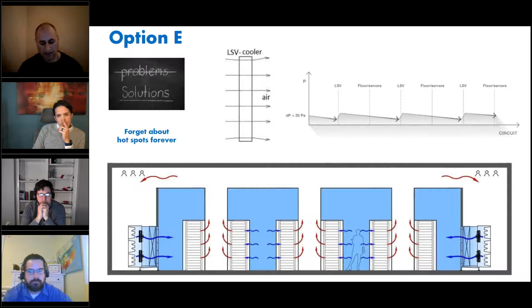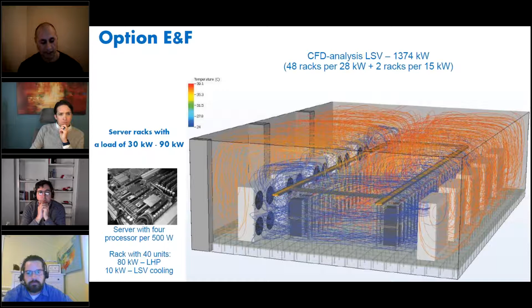You see CFD modeling, which was carried out by our customer for a hall with 48 racks with an average power of 28 kilowatts, which proves the ability of low-speed ventilation to work with high-density racks. There is also a solution with loop heat pipe that allows you to remove up to 500 watts from one processor. When placed in a single rack, 40 servers with 4 processors in each server, we can remove from one rack 80 kilowatts using LHP and another 10 kilowatts using air cooling. I will talk more about this solution later.